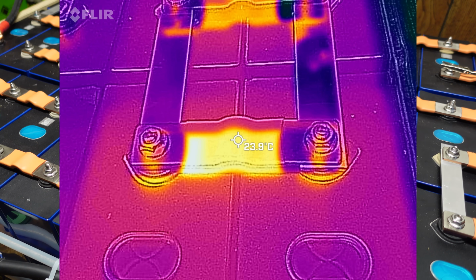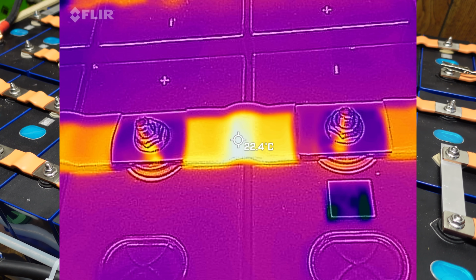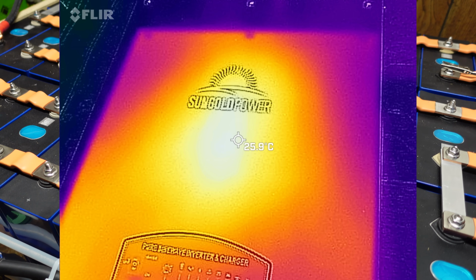And here you can see one of the bus bars that was a parallel connection at 24 degrees Celsius. And then I also checked all the series connections as well. So here's a series connection at 22 degrees Celsius. This connection would have had the full 225, whatever it was, amps flowing through it. So as you can see, these bus bars are more than capable of handling a good amount of power. And the hottest part of the inverter was the top cover, which checked in at 26 degrees Celsius. Other things I noticed included that the output voltage was around 242 volts. My larger AIMS inverter puts out 230 volts. 240 is the NEC standard.